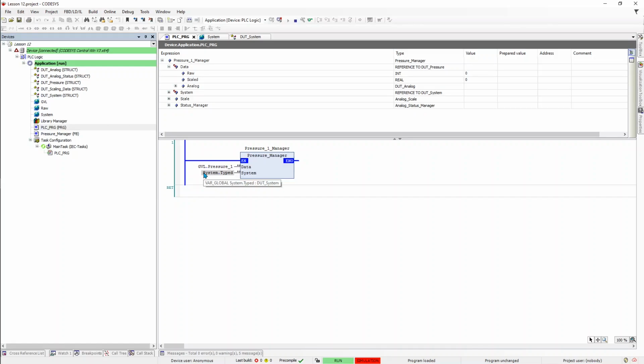You'll fill your PLC up much quicker if you're using big structures and you're copying them on inputs and outputs all the time. I've seen this firsthand in older projects that I've worked with, and there is a massive memory saving to be made using in-outs.